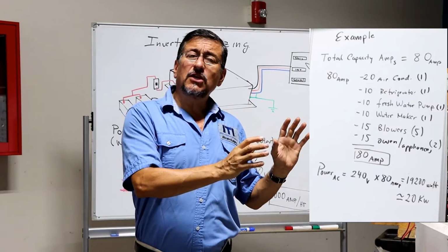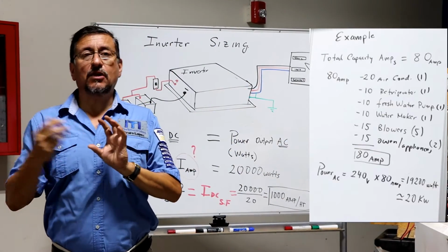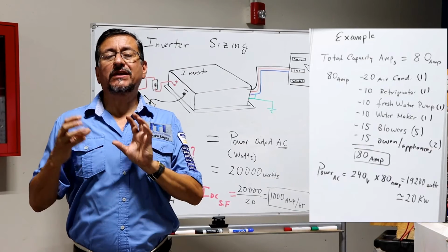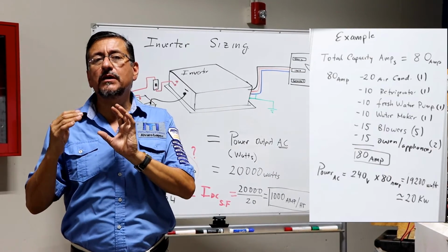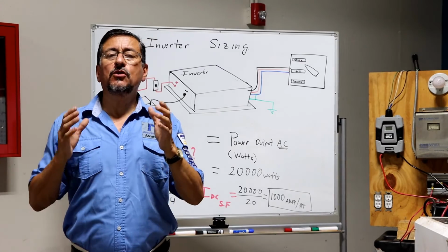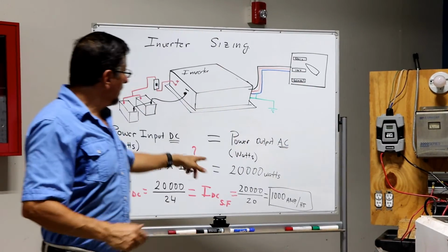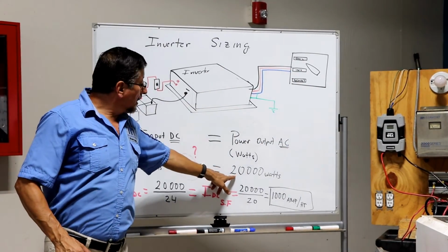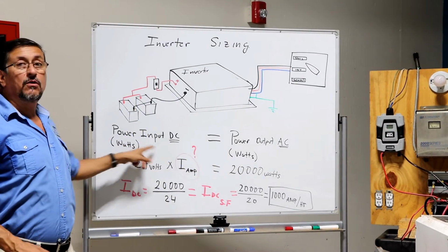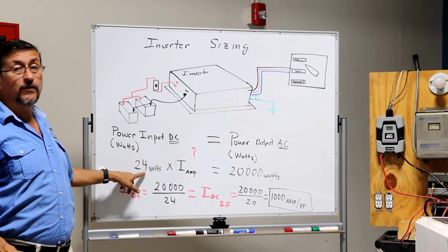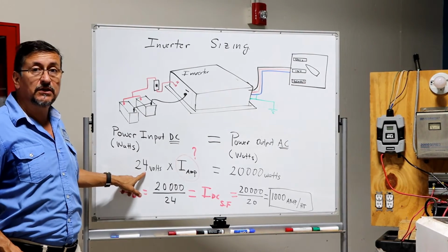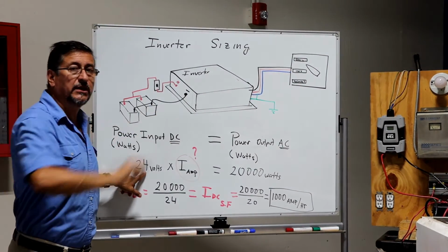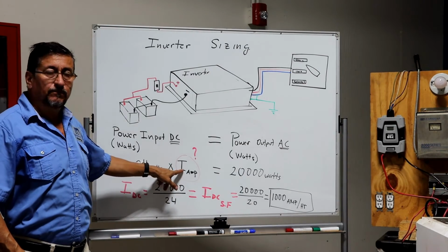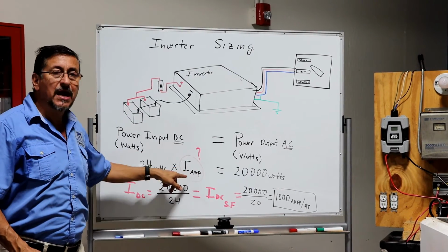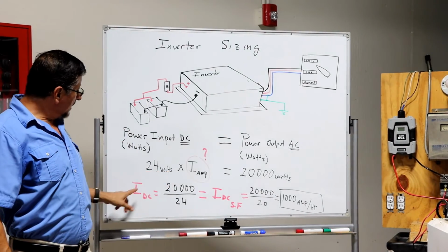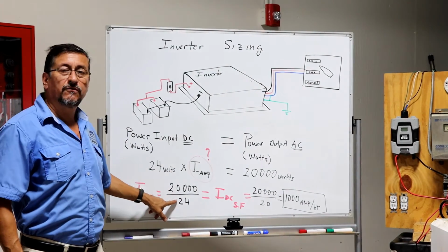That power AC should be equal to the power DC coming in, but the power DC should be a little increased, 20% normally, in order to produce the output power. The output power, 20 kilowatts, should be equal to the input power. The input power is 24 volts, because I am going to organize my batteries in 24. I wanted 240 in the output, times the intensity. And this is the intensity in amps that I wanted. The intensity is 20,000 divided by 24.